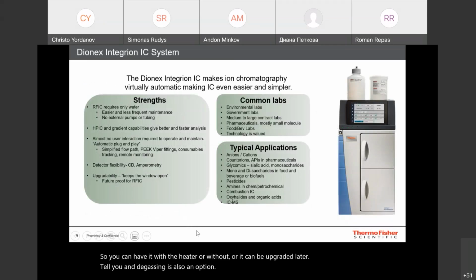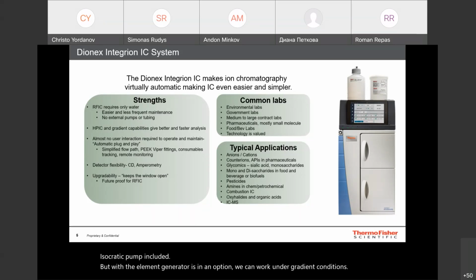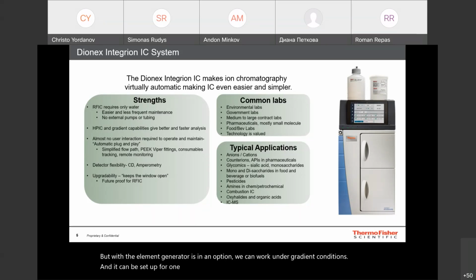If you need a system which allows more applications, also using gradient separations, then we can offer you another system called Integrion. Integrion also has an isocratic pump included, but with the eluent generator as an option, we can work under gradient conditions. And it can be set up for one application, either anions or cations. But gradient separations allow many more applications, also for oxyhalides like bromate, chlorite, chlorate in drinking water.